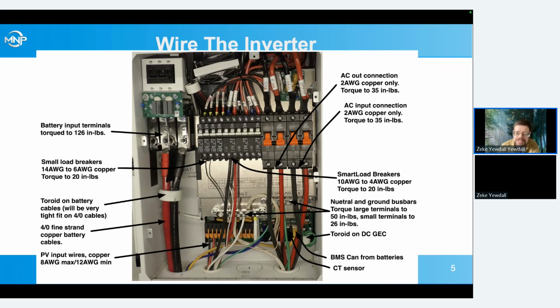Our PV wires, those are a maximum of 8 gauge wire. And our AC connections, one thing to note is all of these breakers are only rated for copper wire. I know a lot of people's inclination is to run aluminum SER cable in and out of the inverter, but the breaker terminals are not rated for aluminum wire, so something to think about.